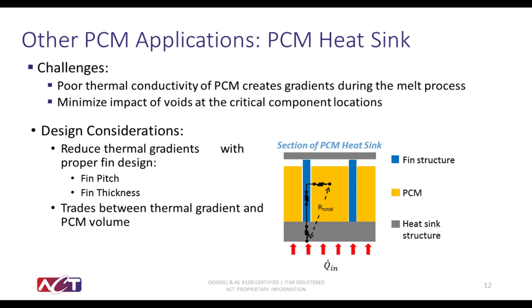The second challenge is managing the voids at the location of critical heat loads. You can see in the figure on the right, a void volume is present to allow for expansion of the PCM during phase transition. In most cases, where orientation with respect to gravity varies, the location of the PCM when it melts and freezes will vary as well. If there is significant empty space around a critical component, that component can see a large temperature rise before the PCM absorbs the heat load.